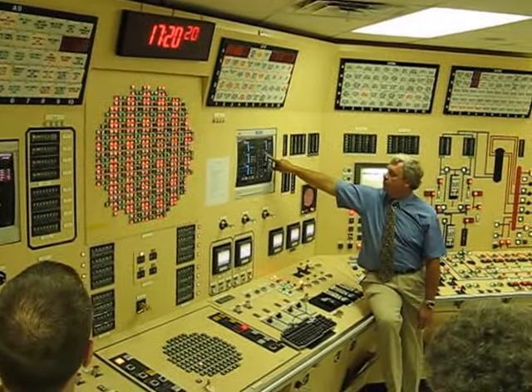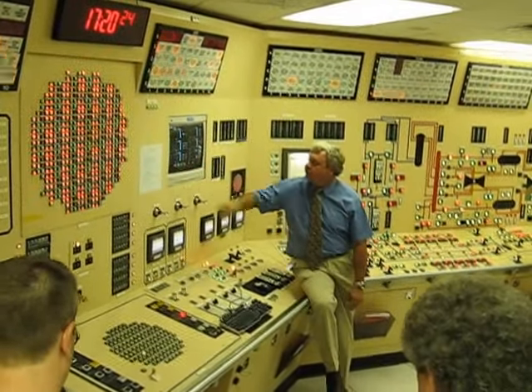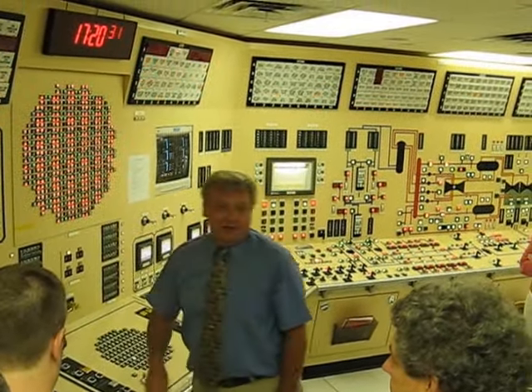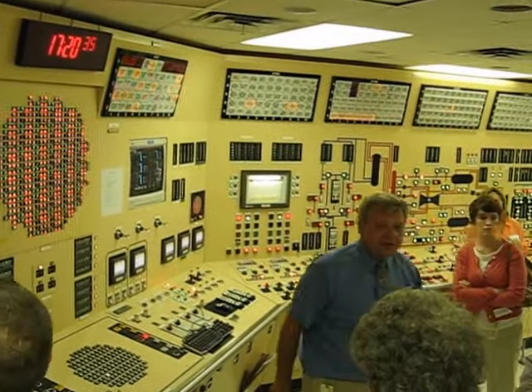We're seconds into this. My wetwell pressure is at about 23 pounds. Drywell temperature is at 210 degrees. All those pumps are running. Reactor vessel pressure is 52 pounds. I've got almost 50,000 gallons per minute of water going into the reactor vessel right now.